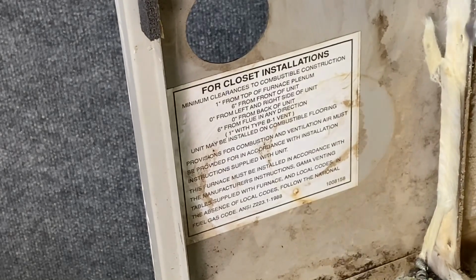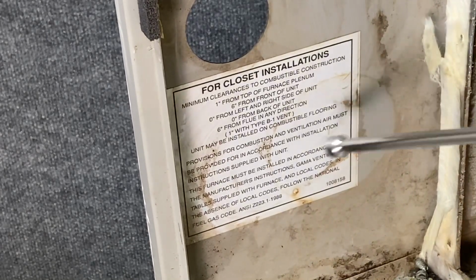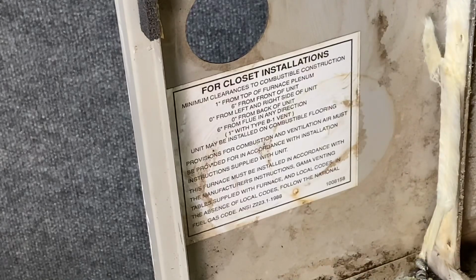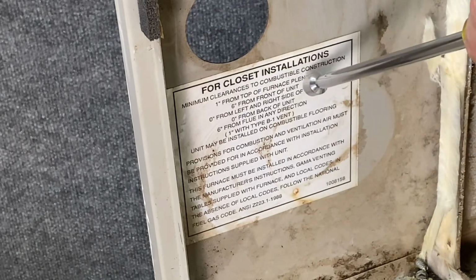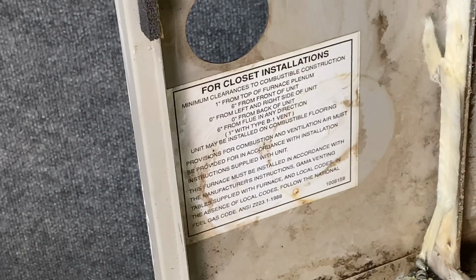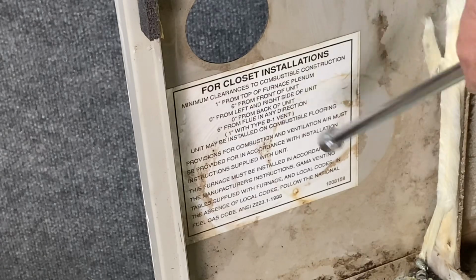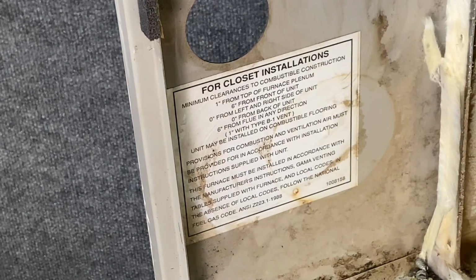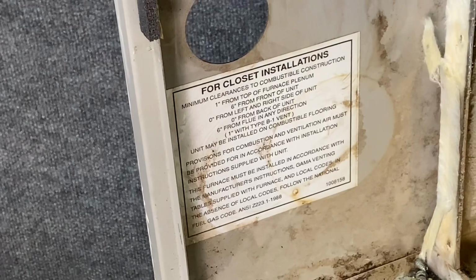Now your code, your city code, may have much longer, much farther distances. What you go with is whichever one is the farthest, whichever one's the safest. So if code says 1 inch and this was to say 5 inches, you'd have to be 5 inches away. If code said 5 inch and this said 1 inch, you'd still have to be 5 inches away. So whichever one's the farthest is the one that you have to go with.